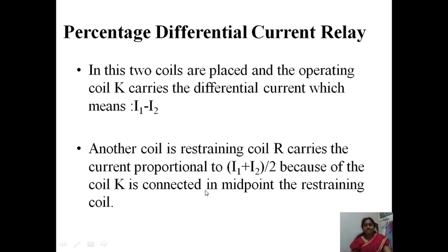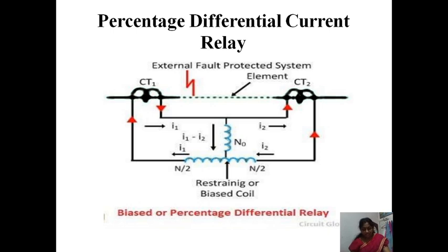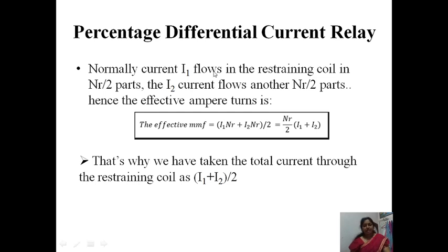The restraining coil R carries current proportional to (I1 + I2)/2, because coil K is connected at the midpoint of the restraining coil. Normally, current I1 flows in the Nr/2 part and I2 flows in the other Nr/2 part. Hence, the effective ampere-turns will be I1·Nr + I2·Nr divided by 2, which equals Nr/2 × (I1 + I2). That is why the total current through the restraining coil is taken as (I1 + I2)/2.